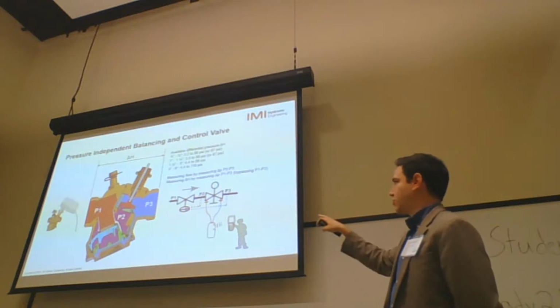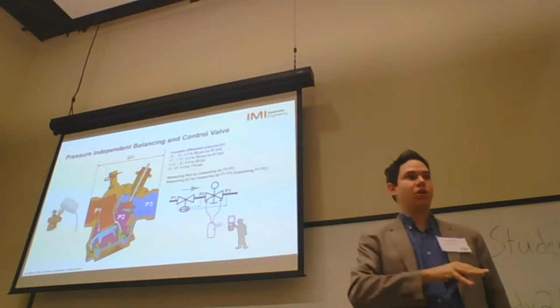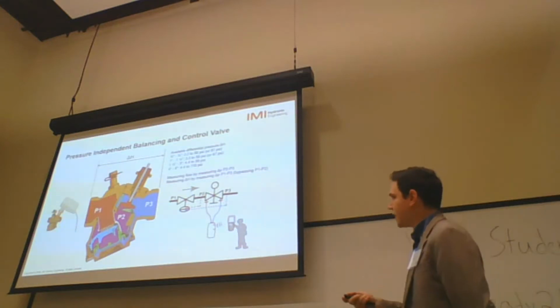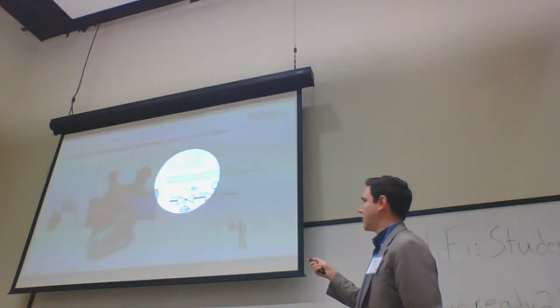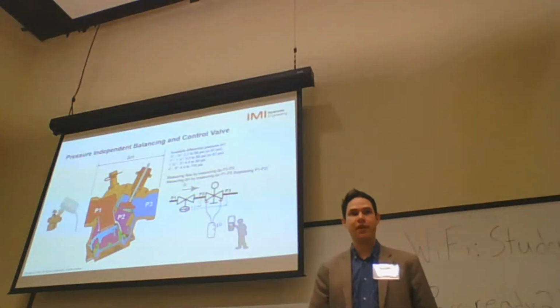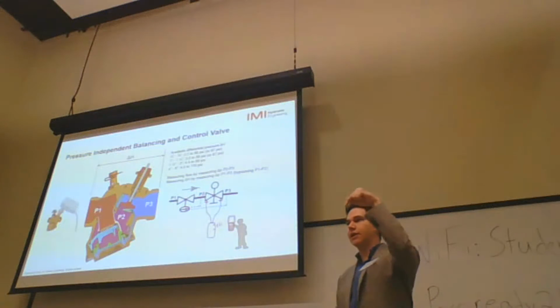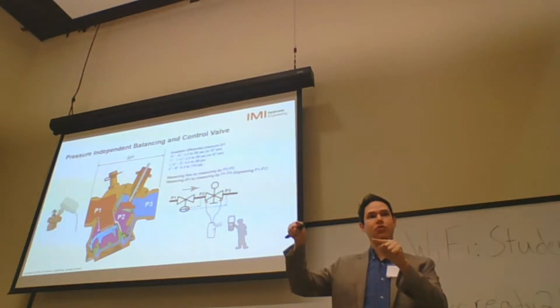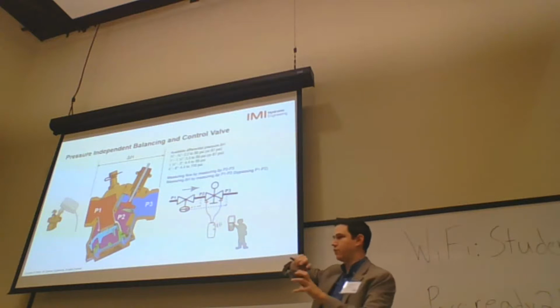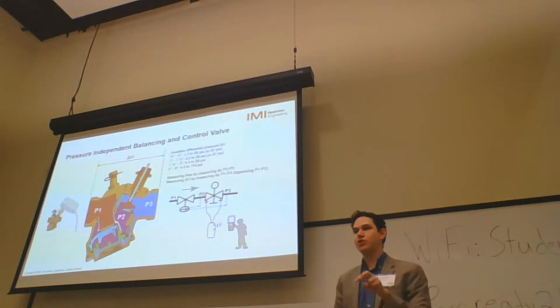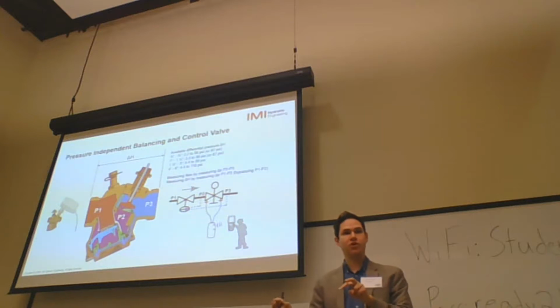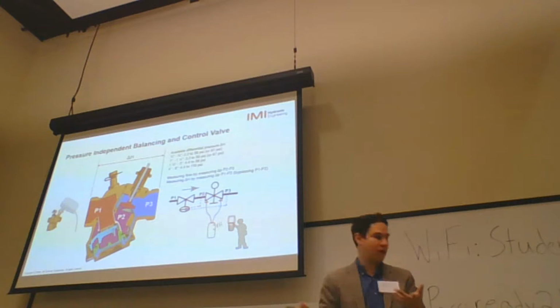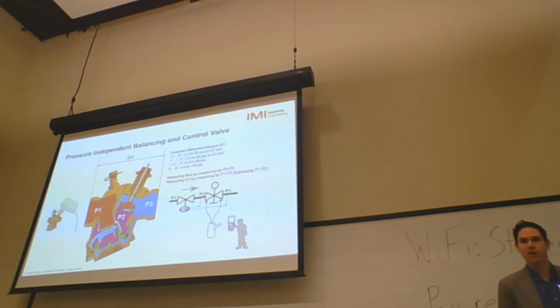What is the difference between this pressure independent control valve compared to any other pressure independent control valve in the market? This is the only one where you can measure the delta H, or the available pressure. It does have a function on this PT port right there. This PT port you can open with the Allen key and basically bypass the DP controller. And when you bypass the DP controller and you fully shut the valve, you are able to measure the available pressure. And what we call the available pressure is the pressure getting into the valve. You can easily do that with a manual balancing valve. So you can basically fully close the manual balancing valve and measure the differential pressure. It's what we call the available pressure.